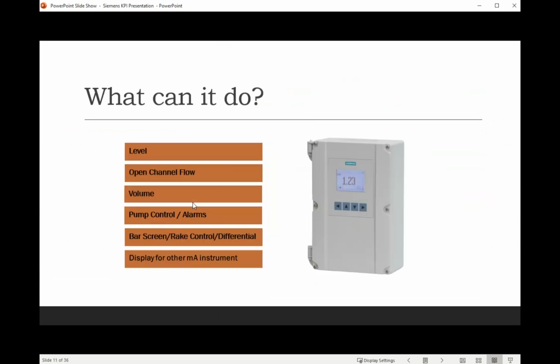All right, so what can the Hydroranger do? So basically, a Hydroranger in its basic form can do ultrasonic level measurement. But at the same time, we can also do open channel flow measuring with a flume or weir. We can do a volume calculation with the Hydroranger. We have the 6 relays, so we have the ability to have pump control and alarms. Specifically for pump control, we've got fixed duty assist and alternate duty assist algorithms built into the 6 relay Hydroranger. Then we also have the ability for bar screen and differential control when you're in a channel, and it kicks on a relay when the differential reaches a certain height.